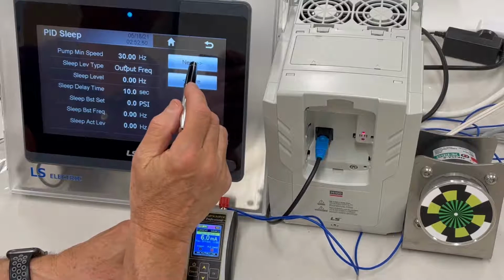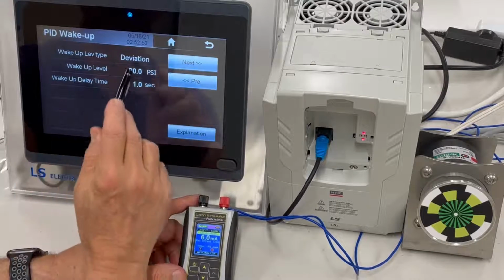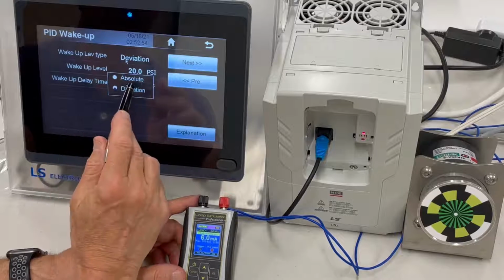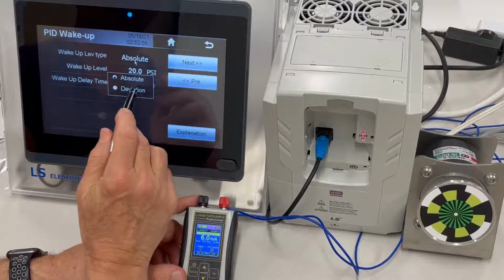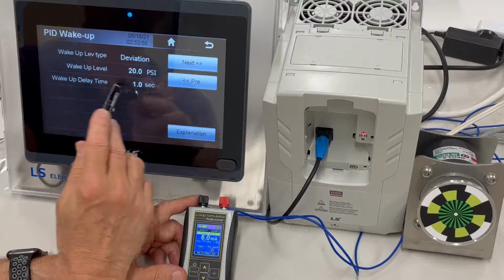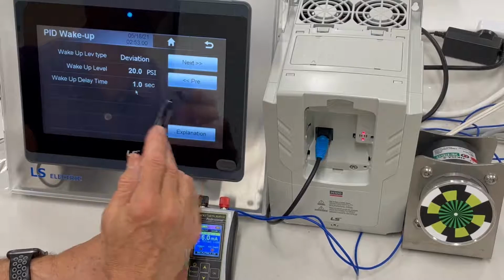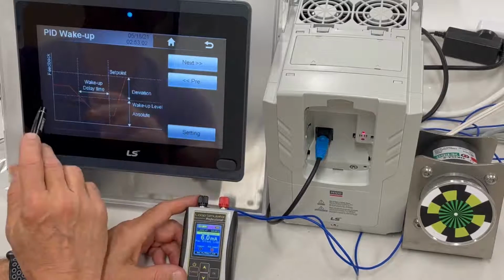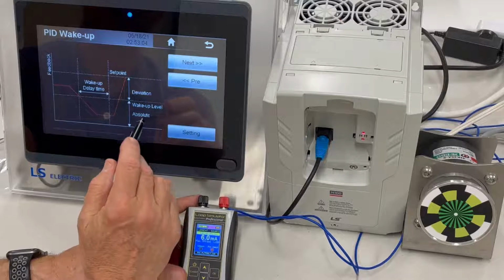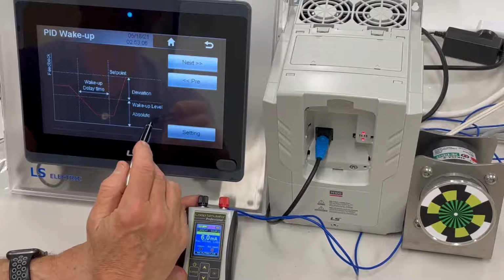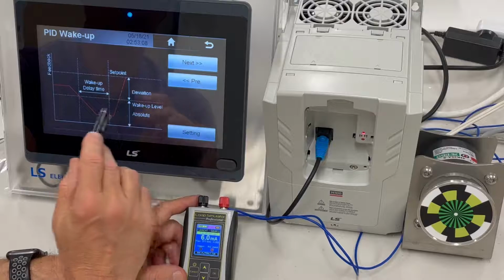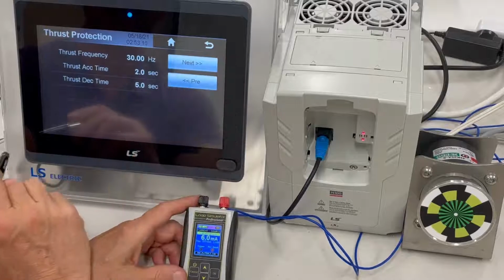I won't bore you by going through them all. Wake up type is deviation. You also have a choice for absolute, but in this case, we're going to use deviation. Wake up PSI is 20, and wake up time delay is 1 second. And here's an explanation to show you the difference between deviation and absolute, where the ranges are and how they're deployed graphically.